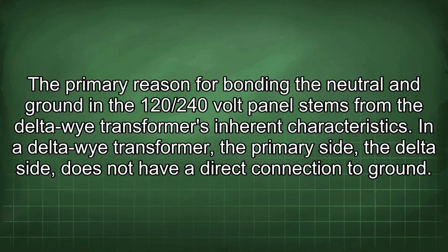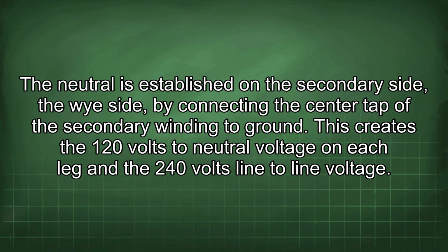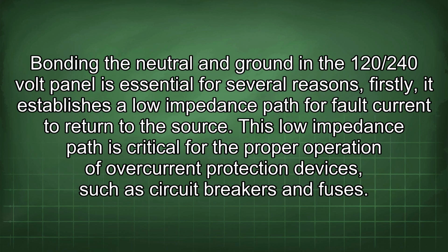In a delta-wye transformer, the primary side, the delta side, does not have a direct connection to ground. The neutral is established on the secondary side, the Y side, by connecting the center tap of the secondary winding to ground. This creates the 120 volts to neutral voltage on each leg and the 240 volts line to line voltage.